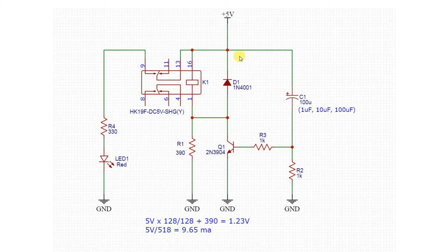And then at this point, current will flow down this path through the K1 coil into R1 to ground. So at this point we'll have our holding current and our holding voltage governed by the value of R1. And down below here is how I calculated the R1 value.